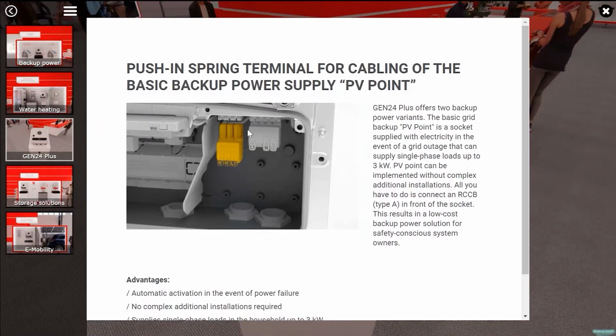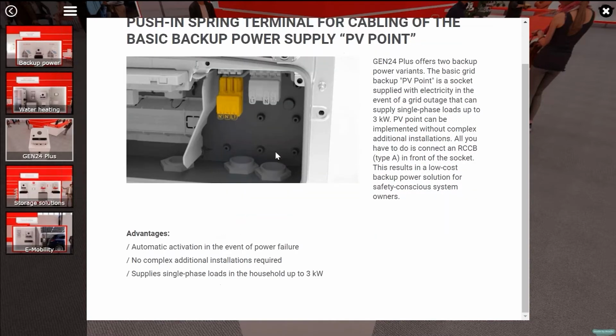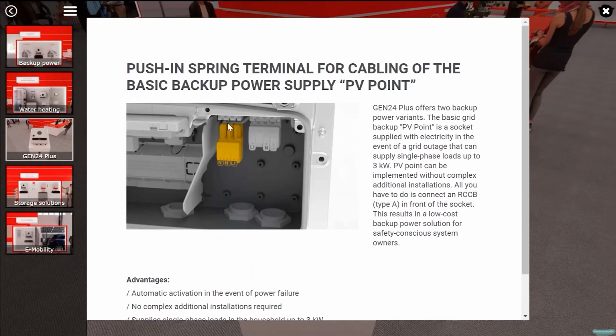On the AC side, you'll see two connection points. One is called a PV point - this is for your backup as an option - and this is your normal AC connection. With the PV point, you have that as an option, and you also have a full backup as an option. We'll talk more about the PV point, but here you can see it's the same spring release clamp that we have on the DC and AC side.